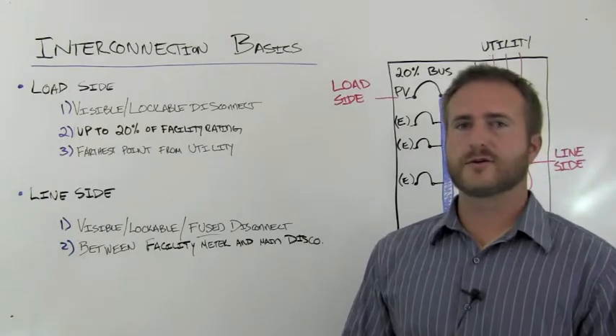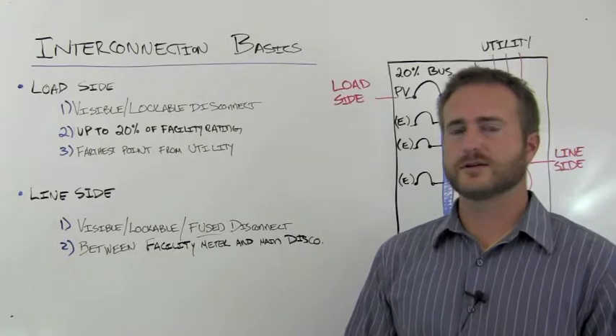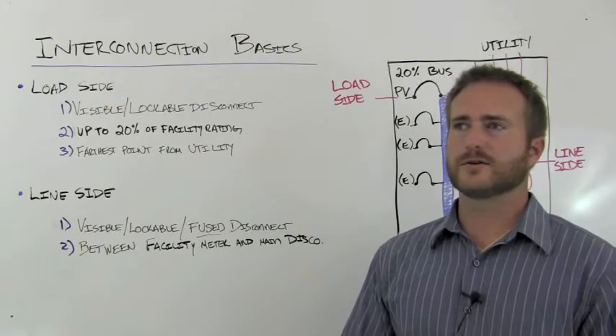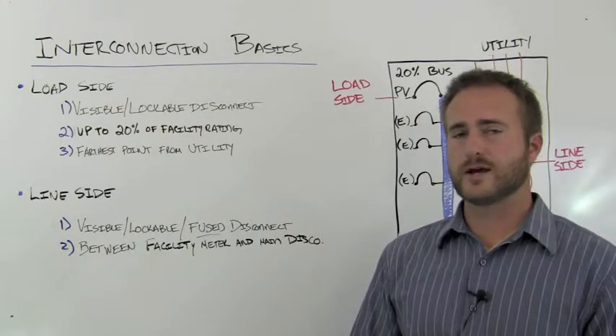The load side has three main points you need to keep in mind. You're going to need to install a visible lockable disconnect for the utility to use. You're going to need to install up to and limited to 20% of your facility's main rating.